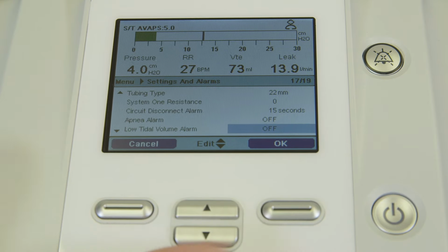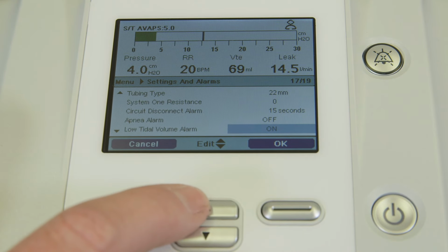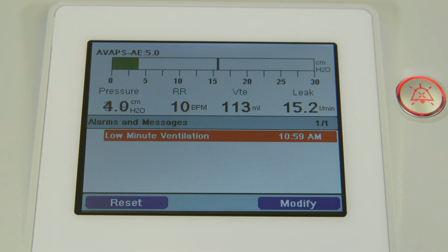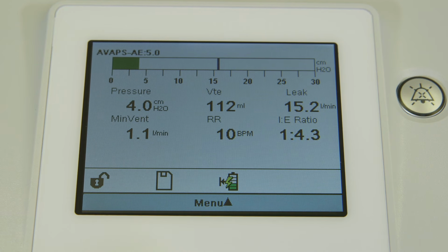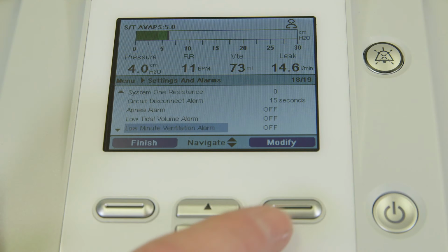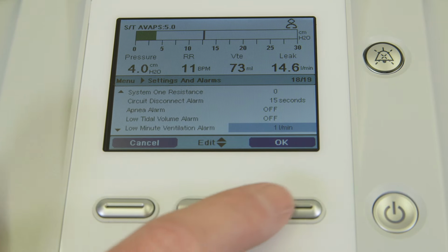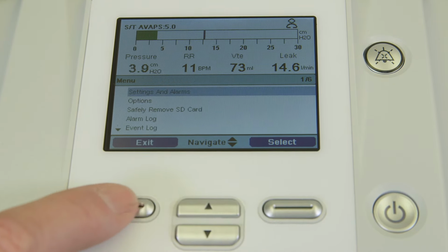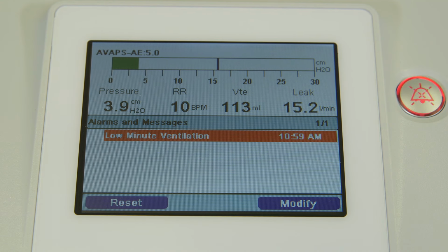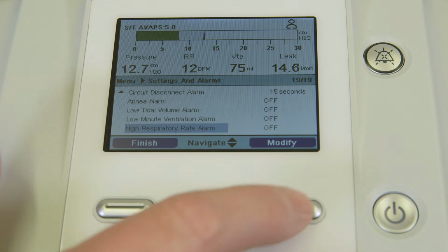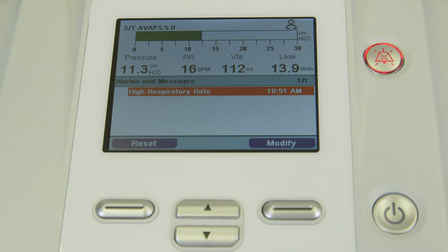The low tidal volume alarm is a high priority alarm that occurs when either the AVAPS or AVAPS AE mode is enabled and the target tidal volume cannot be reached. Once the target tidal volume is reached, the audible alarm will terminate. The low-minute ventilation alarm activates when the calculated minute ventilation is less than or equal to the setting. This high-priority alarm will continue until the estimated minute ventilation is greater than the low-minute ventilation alarm setting. Finally, the high respiratory rate alarm activates when the measured respiratory rate reaches or exceeds the selected setting.